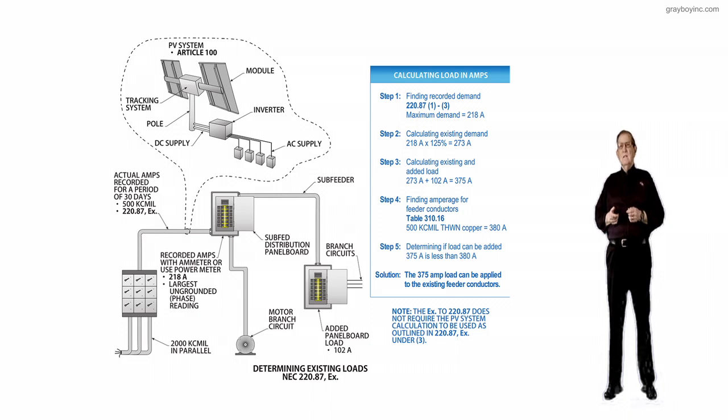So you have to check with the authority having jurisdiction if you do that, though, and see if they will accept that type of calculation without going to Table 310.16 to determine the ampacity of those conductors and how the load was calculated and so forth.